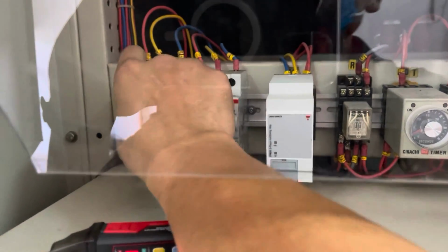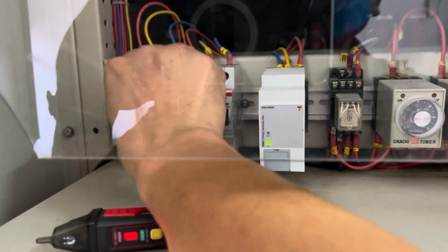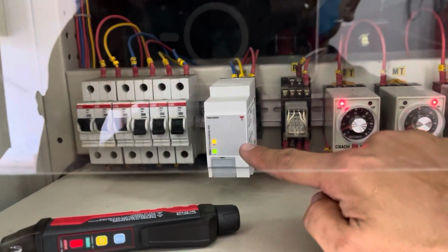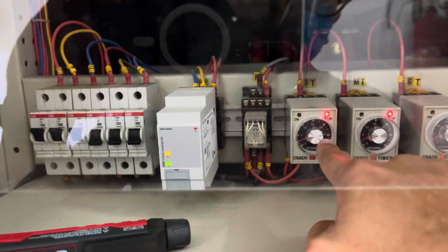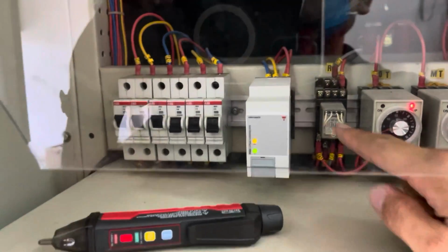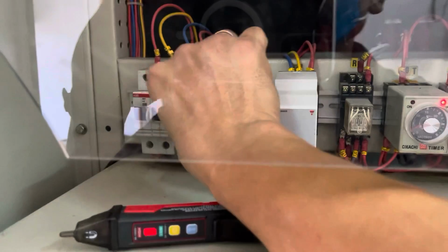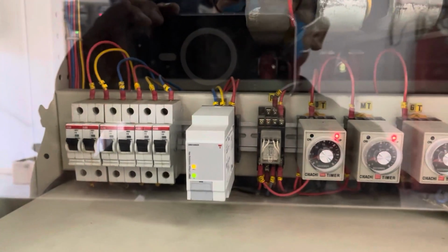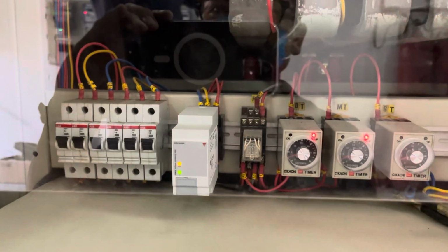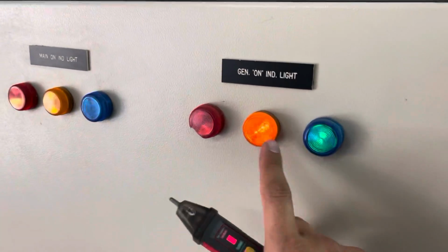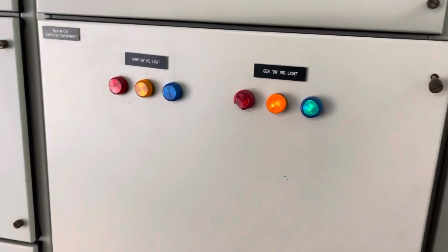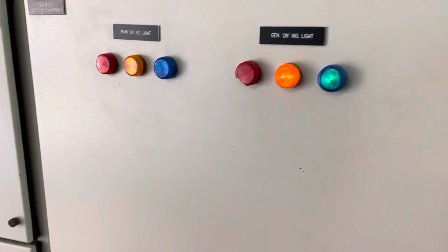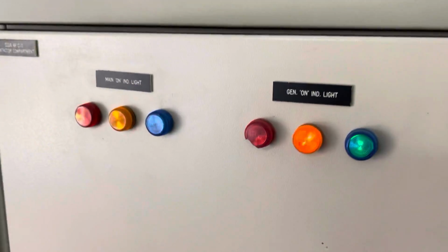We on the main supply MCB first, to allow this one to be in function first, timer relay stable, alright, then only we switch on the genset MCB. Okay, so this is what we call normalize. How do we know? Here, the genset is running now. Okay, after 3 to 4 minutes, the genset will stop automatically.